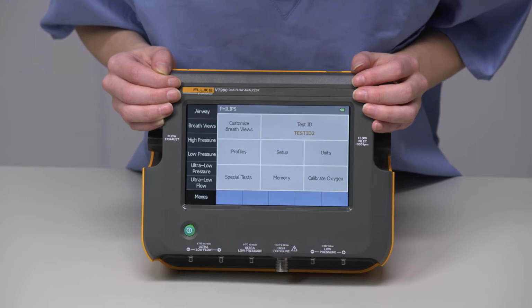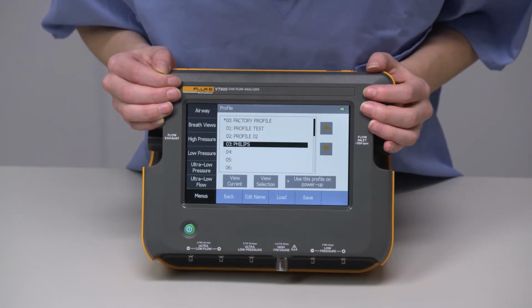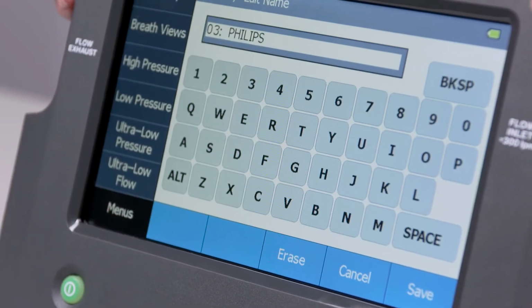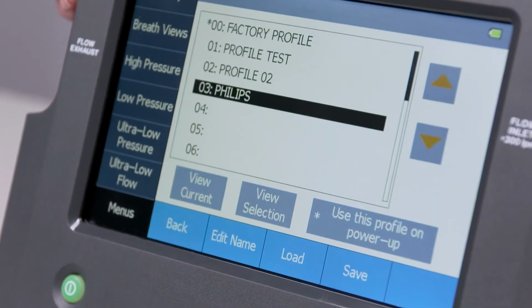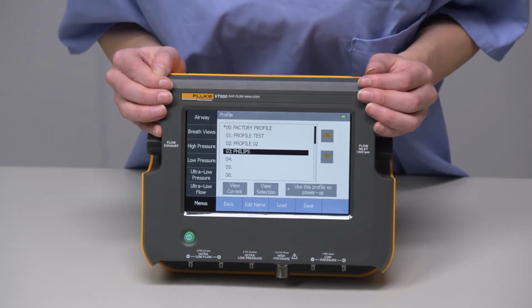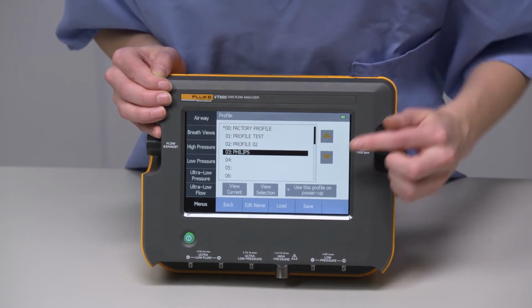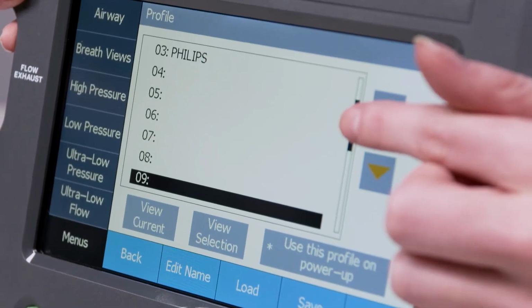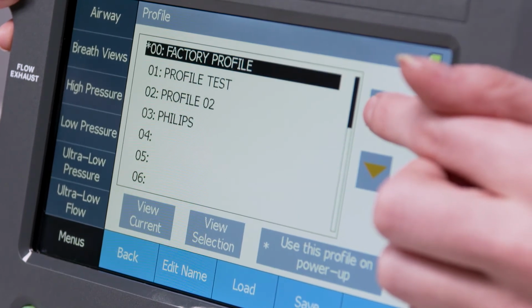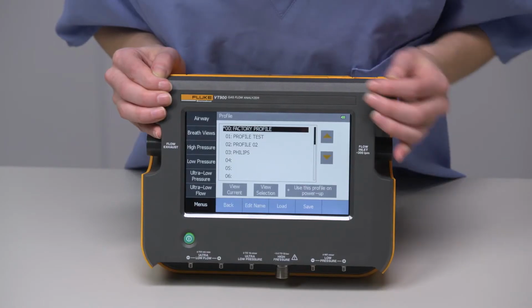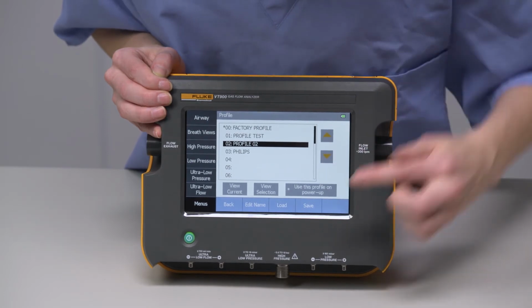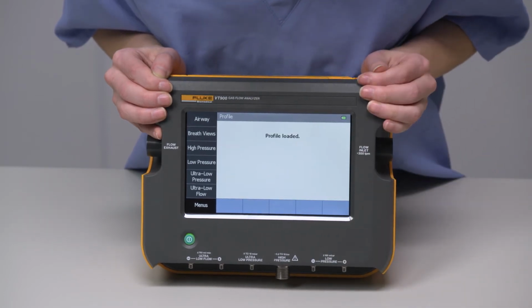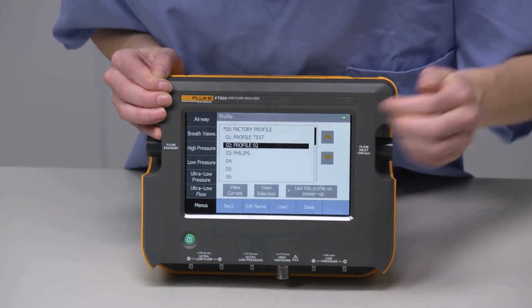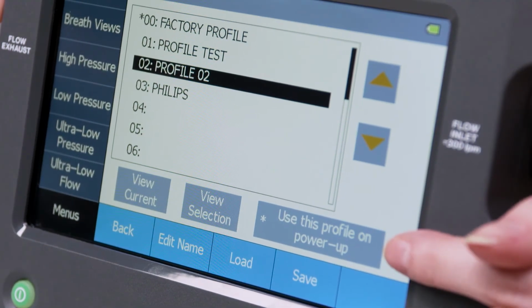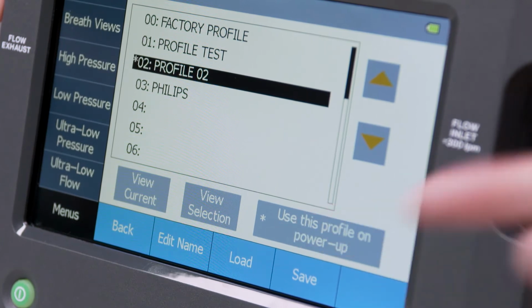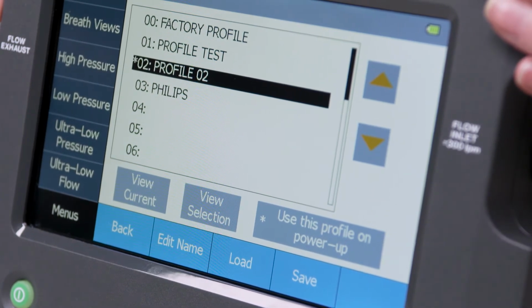It's best to name the profile right away. To do this, click Edit Profile, then press Save. Your profile is now saved and ready to use for a future test. You can now see the list of all saved profiles. You can create and save up to 20 profiles. To use a different profile than the one you're on, highlight it, then press Load. If you prefer to always test with a certain profile, you can set it so that when you power on the device, it will be automatically set to your profile preference, and you don't have to set up the test device.